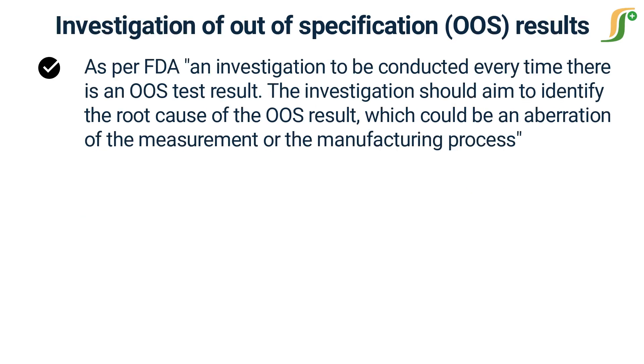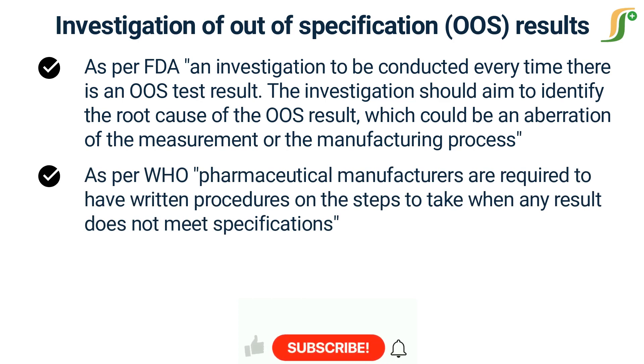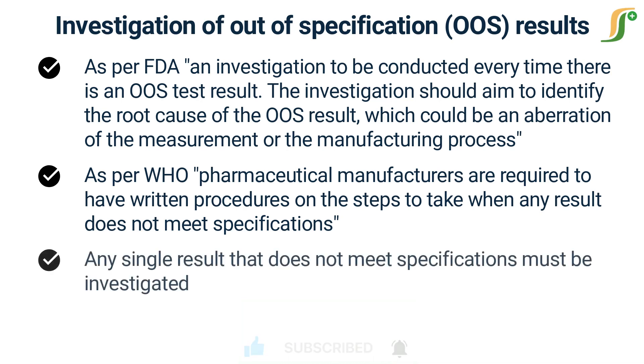FDA regulations require an investigation to be conducted every time there is an OOS test result. The investigation should aim to identify the root cause of the OOS result, which could be an aberration of the measurement or the manufacturing process. Regulatory authorities are very sensitive to how any out-of-specification test result should be handled. OOS rules require that any single result that does not meet specifications must be investigated and not discarded without written justification or evidence that it was a genuine analyst error.